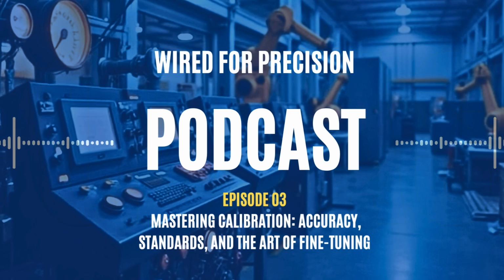Let's talk about the actual tools and methods technicians use during calibration. The right tool not only ensures accurate calibration, but also improves efficiency, safety, and documentation integrity. Some of the most widely used tools in the industry include multifunction calibrators. These devices can simulate and measure voltage, current, especially 4 to 20 milliamps, RTDs, thermocouples, frequency, and more. Great for technicians who handle a variety of field instruments. Documenting process calibrators go a step further by recording calibration data on the spot and generating reports or certificates. They help ensure compliance with ISO, FDA, and GMP documentation requirements.